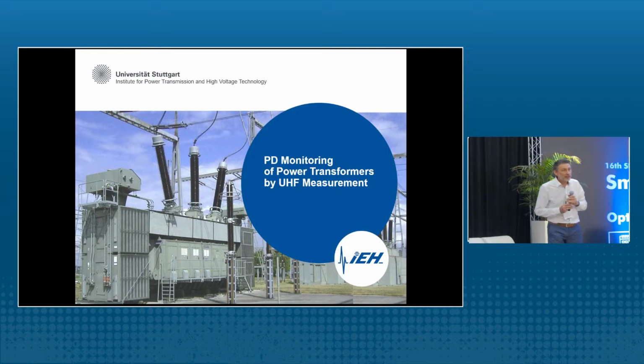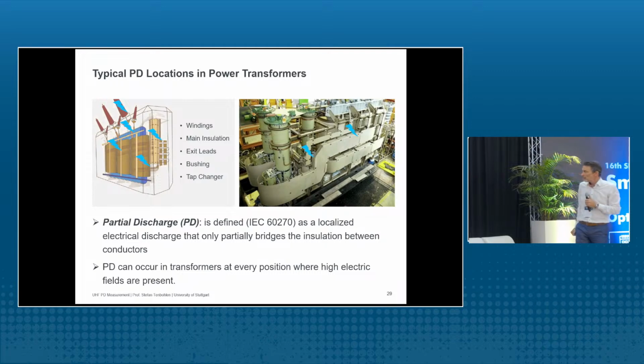Okay, let's come to the last point, PD measurement on a transformer. Yeah, time is good. What are PDs? PDs are partial discharges, and partial discharges appear if you have a very high electrical field strength at a certain position. For example, if you are standing under a high voltage line, you can hear this noise, this corona noise. Yeah? There are some small sparks on the transmission line, and these corona discharges are partial discharges.